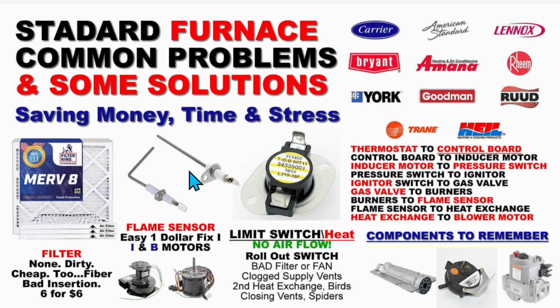The biggest service call probably in the HVAC industry is for a dirty flame sensor. These things are metal rods. They're not really replaceable. Just take a dollar bill or any relatively new bill, and I'm sure it works in different countries too, or take one of those green pot scrubber pad things and just scrub it and get the dirt out. Because remember, that flame sensor has to verify to the control board that there is flame. And if it can't do it because it's dirty, between 3 to 5 seconds, your furnace will shut down. It's going to try to restart, then it's going to shut down. It always tries to do this sequence 2 or 3 times before it goes into a shutdown for 3 hours. So that's how that works.